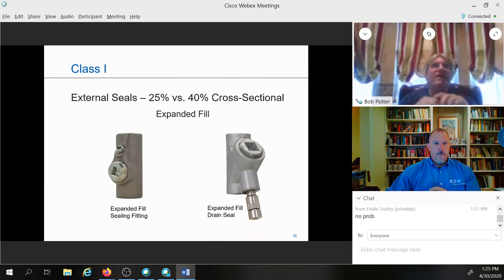In that particular case, what I recommend for people as an approved sealing method is the same epoxy that you would use with the cable gland that stops the gases from entering the cable core. So when that cable in my conduit enters the enclosure, inside the enclosure, I would separate the particular conductors and put that epoxy in between the conductors. That's going to stop any possible gas from entering that cable core.